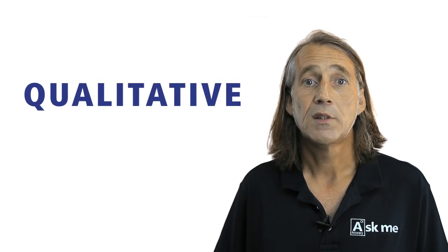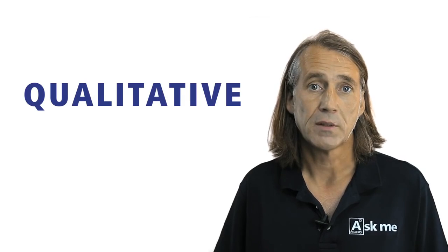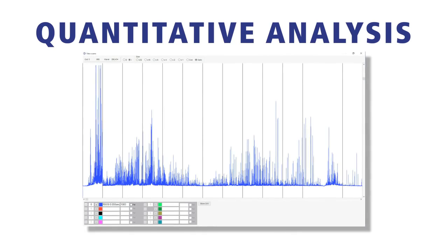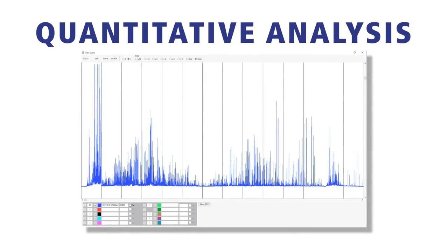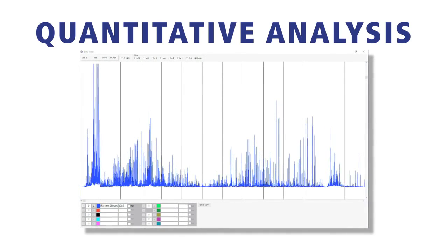This means that OES provides qualitative information about the sample measured. However, OES is also a quantitative technique. As we can see, the peak wavelength identifies the element and its peak area or intensity gives an indication of its quantity in the sample. The analyzer then uses this information to calculate the sample's elemental composition based on a calibration with certified reference material.